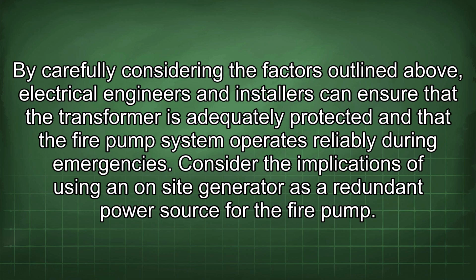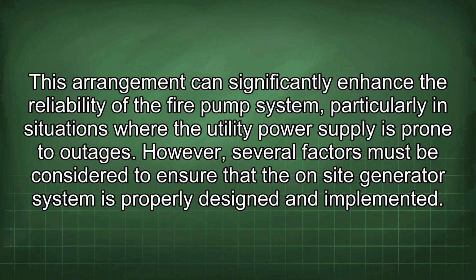Consider the implications of using an on-site generator as a redundant power source for the fire pump. This arrangement can significantly enhance the reliability of the fire pump system, particularly in situations where the utility power supply is prone to outages. However, several factors must be considered to ensure that the on-site generator system is properly designed and implemented.